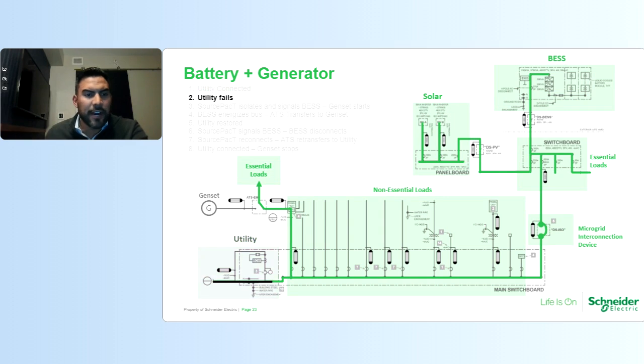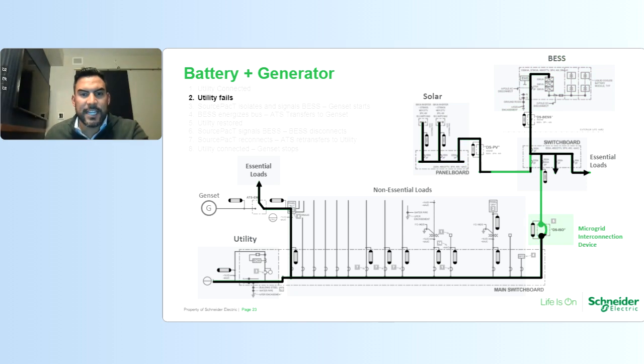When there's a utility outage, your entire system will go dark here. Everything that was once green is now black. These inverters inherently, once they experience a utility outage, are grid interactive devices, so they're dependent on an anchor resource, the utility. When they experience an outage, those inverters shut down, and they will remain shut down until they get some type of signal from a microgrid controller, i.e. a microgrid interconnection device or a more advanced microgrid controller, to signal that we're safely disconnected from the grid.